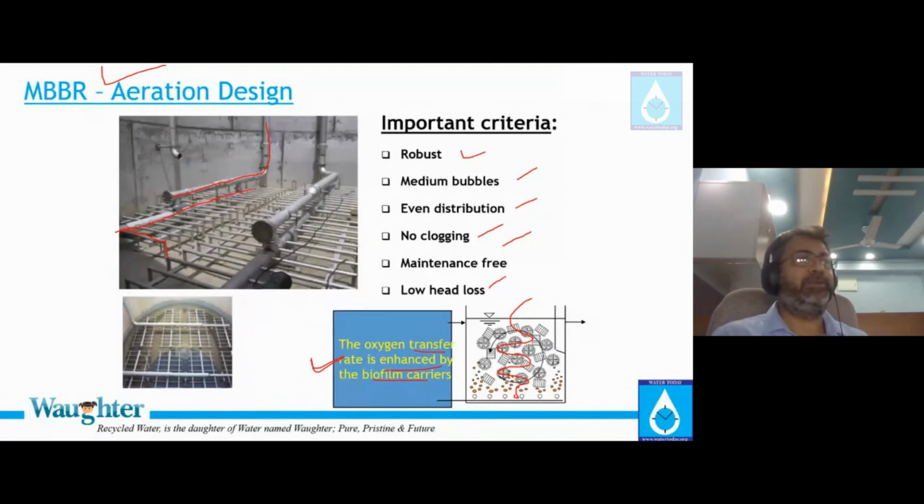So what will happen is, sir, we have invested money, we have put in MBBR technology, but we never find biofilm the way you show it. You will never find it, because engineering-wise you have done a very bad design. You do not have the know-how. This know-how belongs to certain companies and they are experts in that. It is always better that if you are looking for that kind of design, learn from them. Otherwise, just throwing some kind of plastic into an aeration tank does not mean that it will become MBBR.